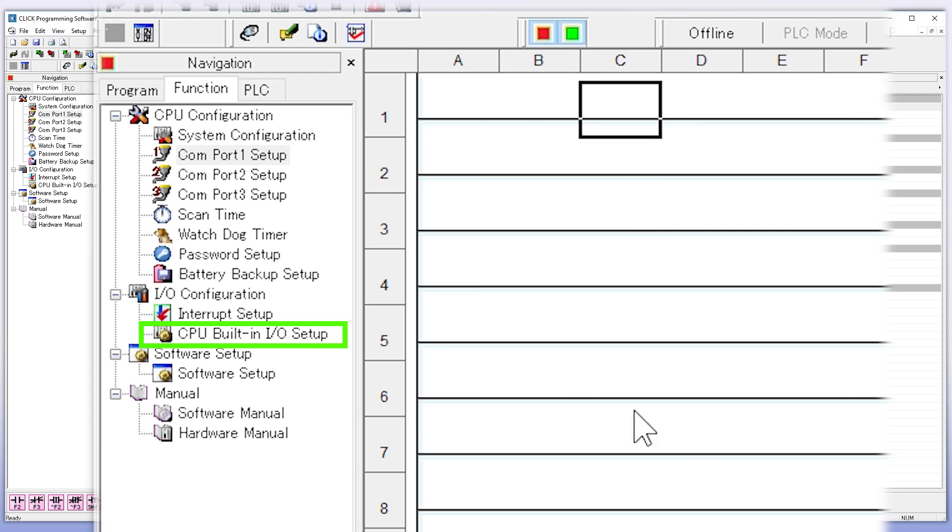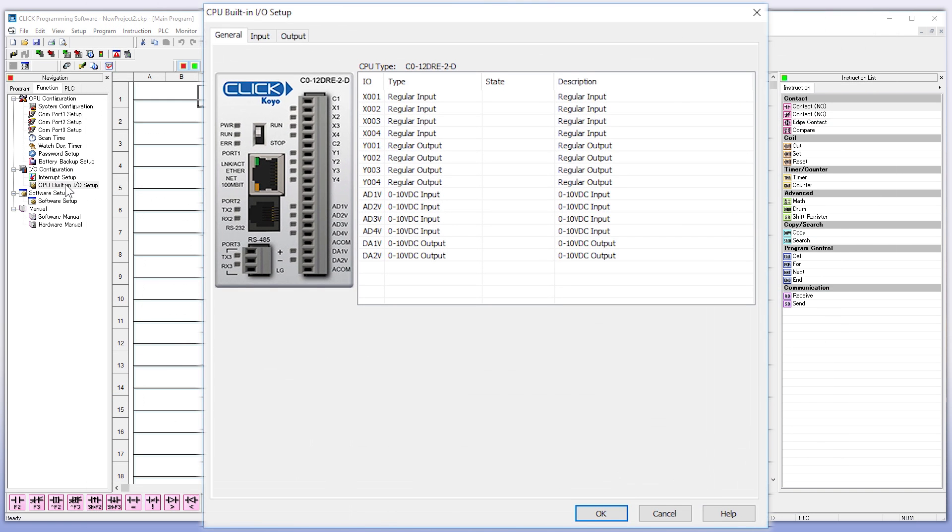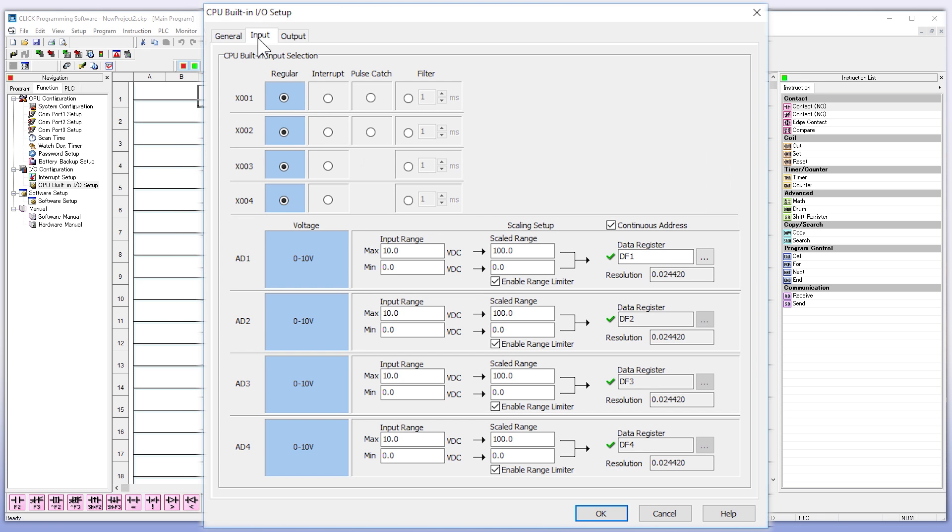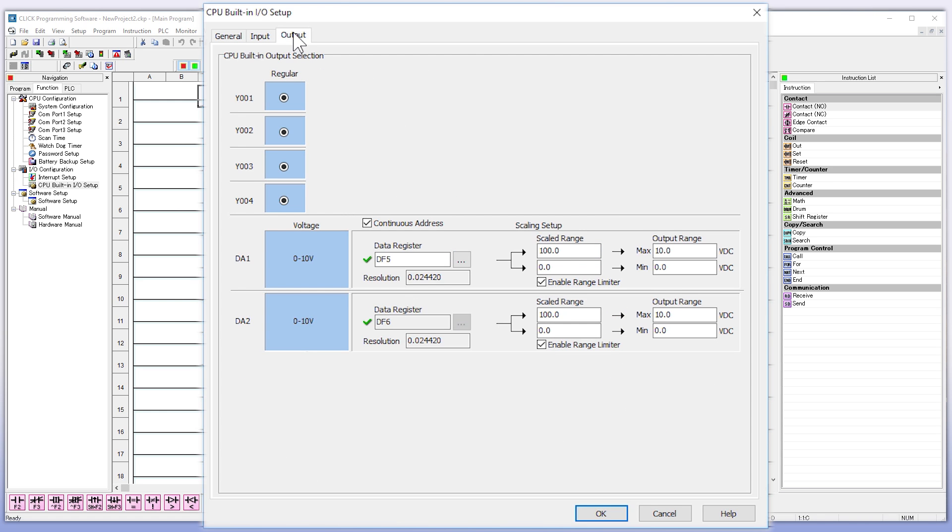Another important spot to highlight here is the CPU built-in IO. The general tab shows all the input and output assignments. Then you have the input and output tab. Here you can make adjustments to the input assignments, and also if you have an analog CPU, you can change the scaling and change the assigned data register.